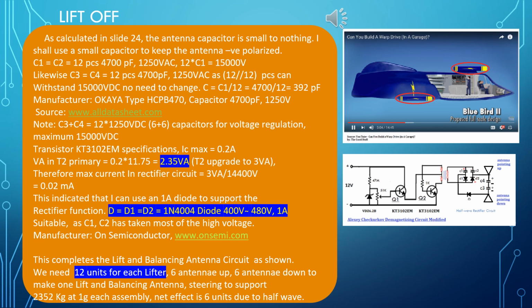T2 upgraded to 3 VA. Therefore, maximum current in the rectifier circuit is 3 VA divided by 14,400 volt, equals 0.02 milliampere. This indicates I can use a 1 ampere diode to support the rectifier function.